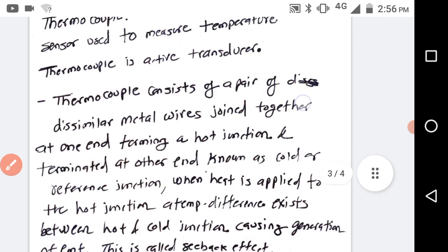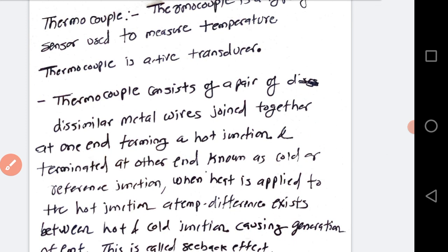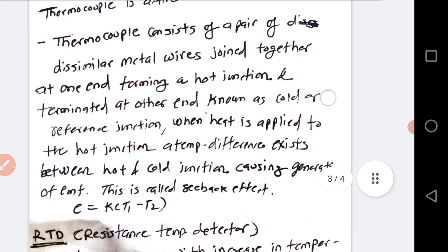So, in thermocouple, temperature is converted to the voltage or EMF. So what is thermocouple? It consists of a pair of dissimilar metal wires joined together at one end, forming hot junction, and terminated at the other end, known as cold or reference junction. When heat is applied to the hot junction, a temperature difference exists between hot and cold junction, causing generation of EMF. This is called Seebeck effect.